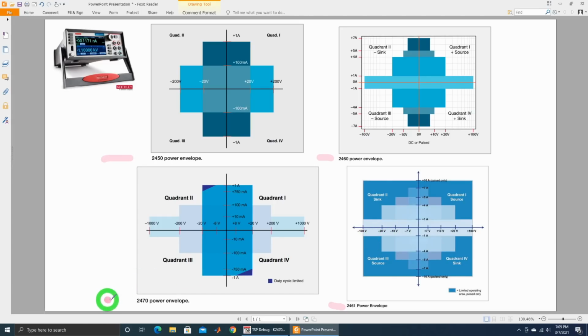The 2470 now finally pushes the SMUs into a high voltage regime, allowing it to go to plus or minus 1000 volts. So this is now all of a sudden excellent for next generation semiconductor processes. For example, in gallium nitride design, you do want to have these high voltages and you want to stress test your devices and find out how they perform. And these devices are now very common, especially in high efficiency power supplies. So looking at the power profile of this one, the current is not very high depending on the voltages you select, and really I wish this 200 was actually a little bit to the left and maybe around plus or minus 500 where your current drops to 10 milliamp, and we will see some of that limitation in our experiment.